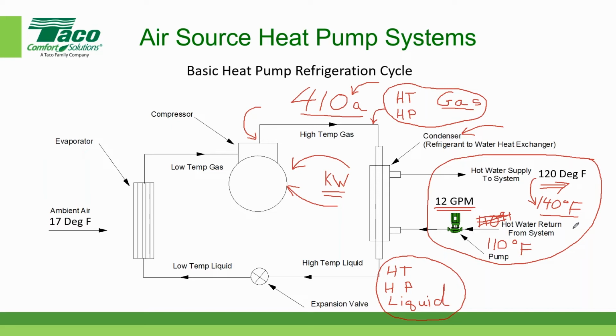Go ahead, Brett. Since you said variable speed, does a variable speed compressor mean the system has variable refrigerant flow? That's true. That's absolutely true. And then obviously, since there's different, you could have different delta T's, correct? Yes. So that's why I have a range of temperatures that you can send out.